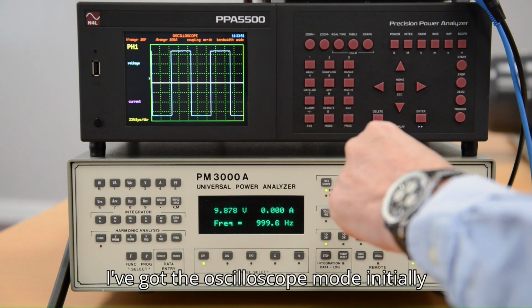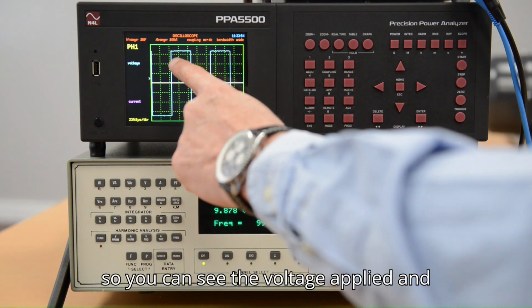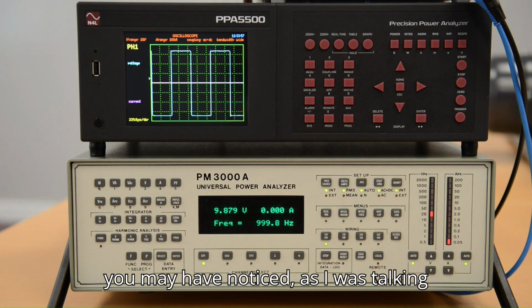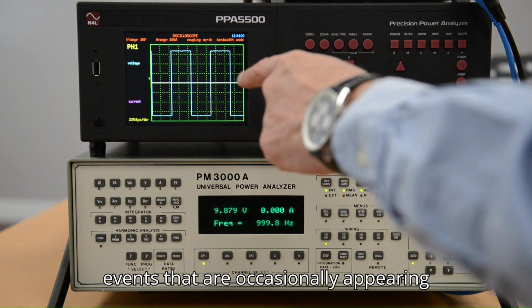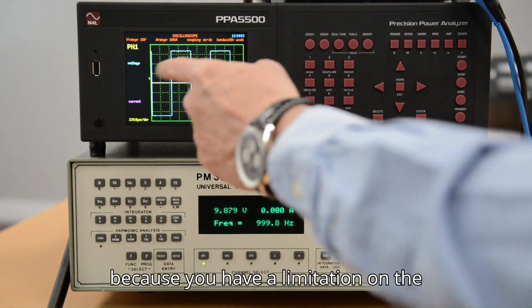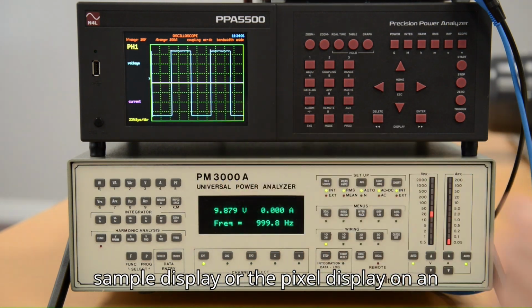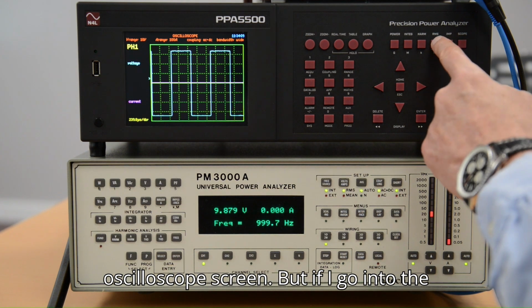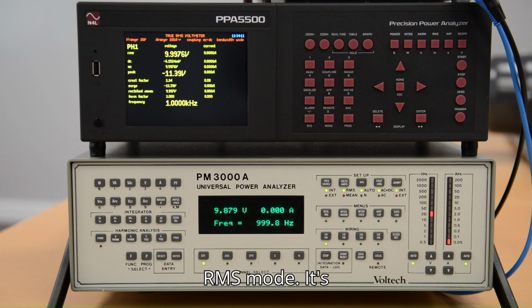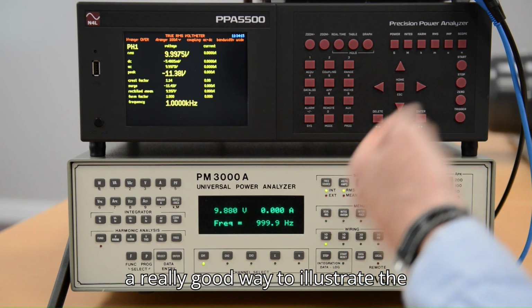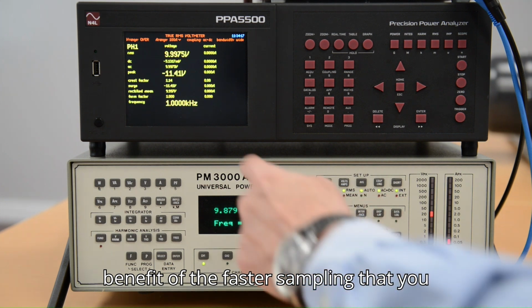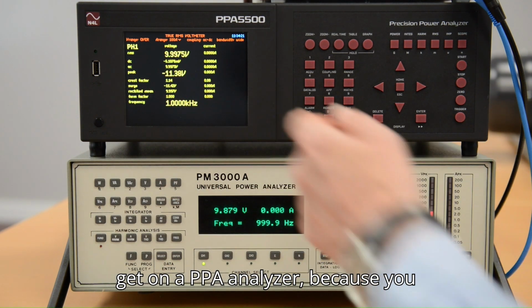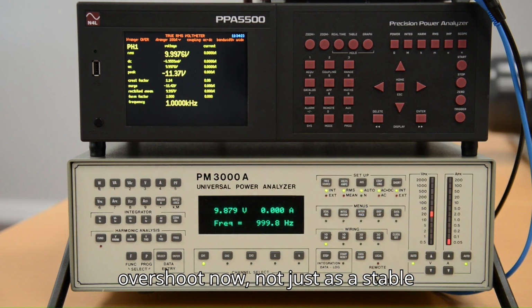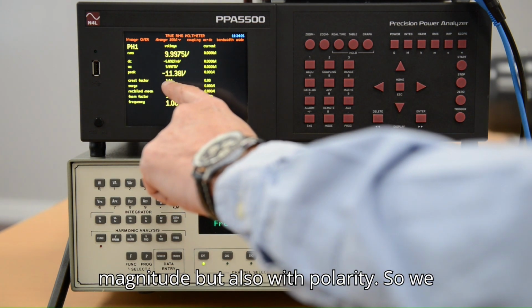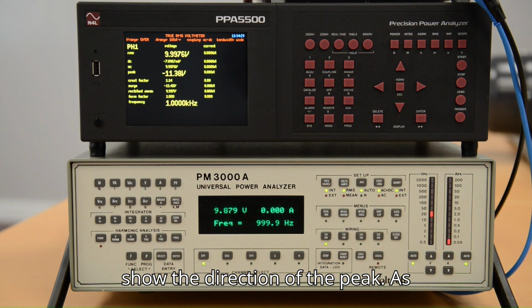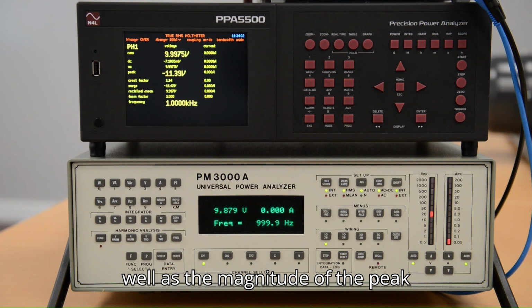I've got the oscilloscope mode initially so you can see the voltage applied, and you may have noticed as I was talking that there are some overshoot events occasionally appearing because of a limitation on the sample display or the pixel display on an oscilloscope screen. But if I go into the RMS mode, it's a really good way to illustrate the benefit of the faster sampling you get on a PPA analyzer, because you can see the peak value, that's the overshoot, not just as a stable magnitude, but also with polarity, so we show the direction of the peak as well as the magnitude of the peak.